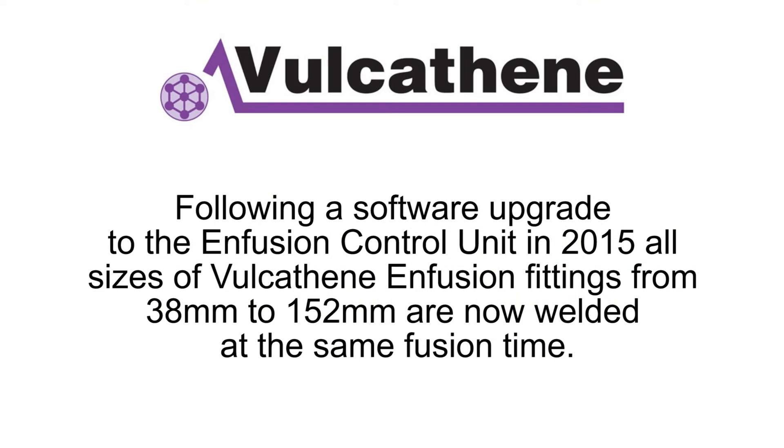Following a software upgrade to the Enfusion Control Unit in 2015, all sizes of Vulcathene Enfusion fittings from 38mm to 152mm are now welded at the same fusion time.